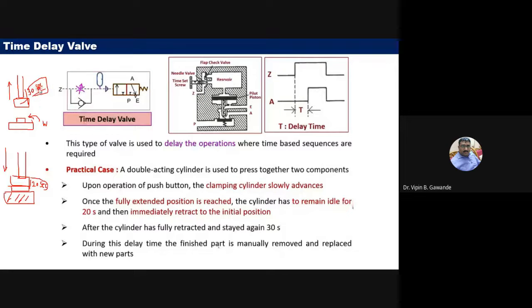In the punching example, a 30-second delay allows placing the workpiece, and a 20-second delay after punching ensures proper contact before retraction. These timings are set using the time-set screw or metering orifice in the time delay valve. The symbol and schematic for the time delay valve represent this functionality.